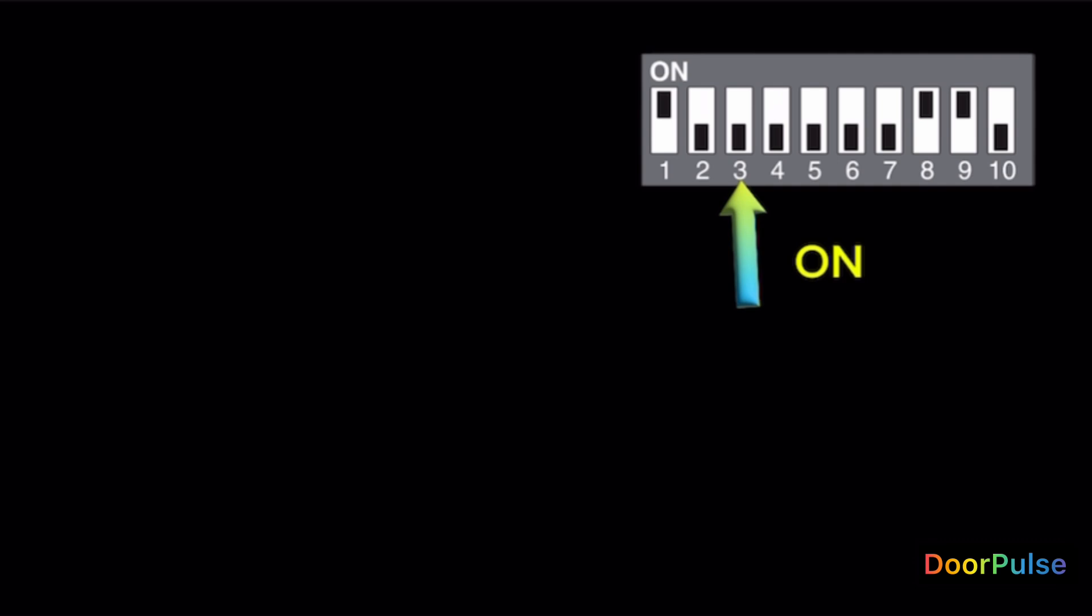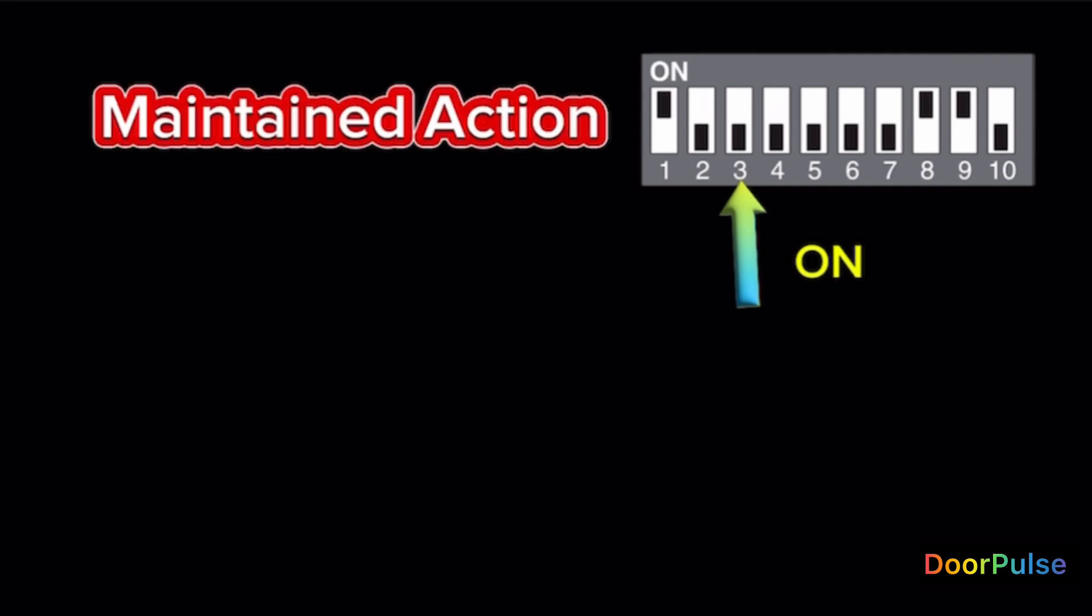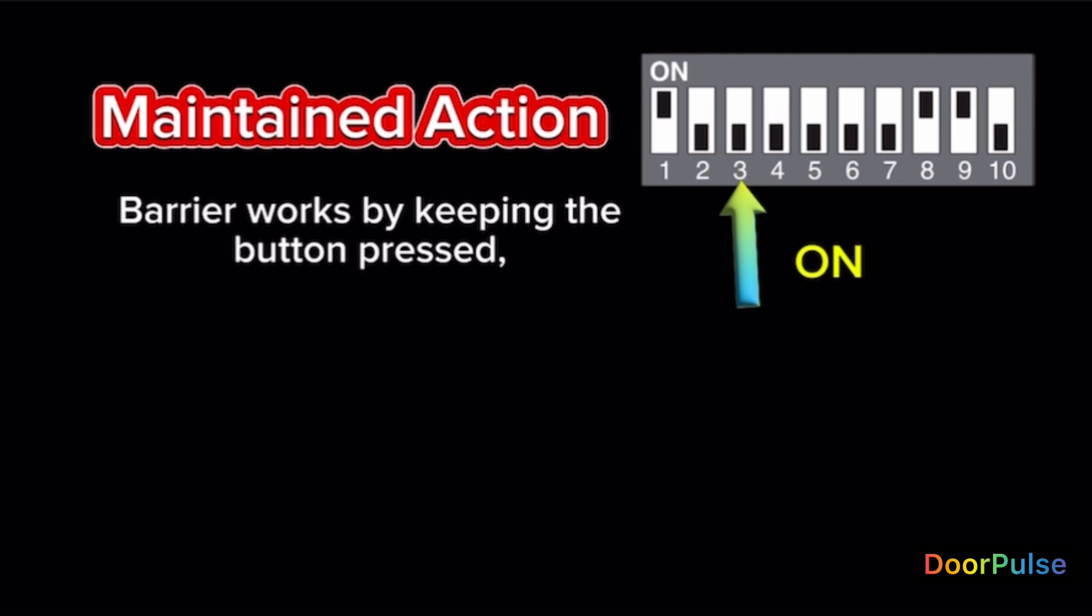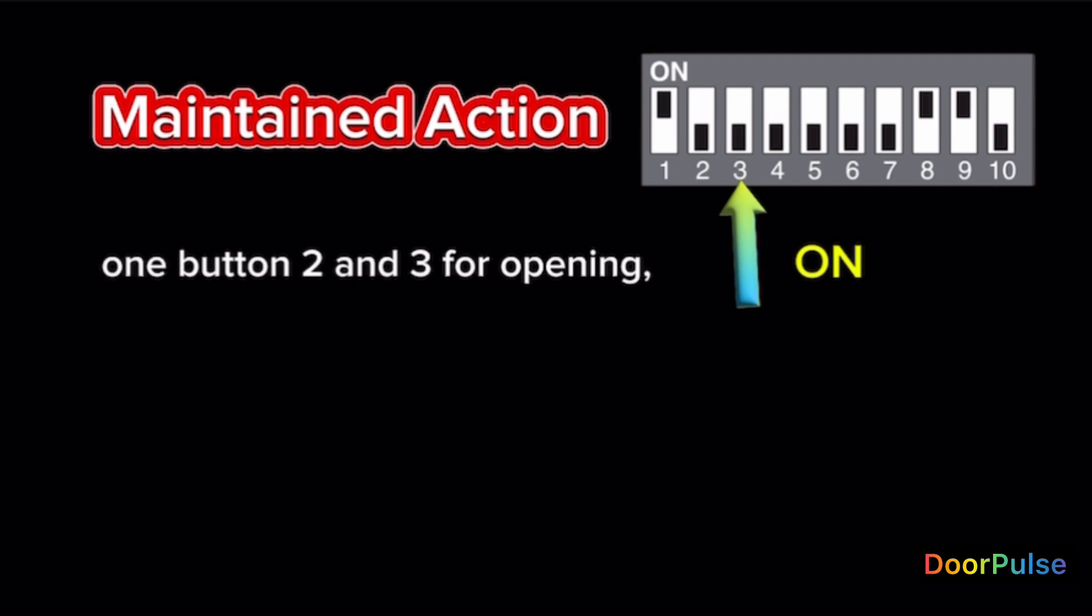Switch 3 ON. Maintained action. Barrier works by keeping the button pressed. 1 button 2 and 3 for opening and 1 button 2 and 4 for closing. This excludes functioning of the radio transmitter.